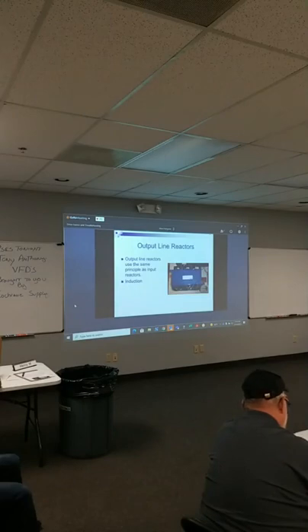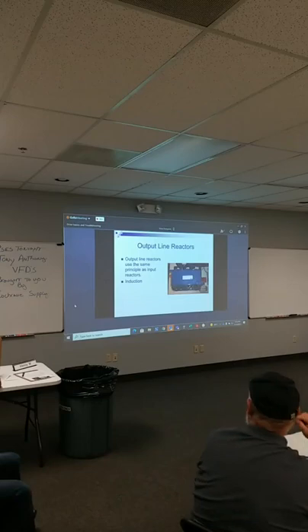Output line reactors, once again, MTE is a very famous, common line reactor. It is the exact same components, basically a fancy coil of wire, and it uses the same principle because they are the same. So what we're doing with the output line reactors, instead of getting rid of the harmonic distortion, is protecting that motor from those high voltage peaks I mentioned, because the way we're pulsing that DC, the peaks are always the same height, and then they get some overshoot. This will actually help squelch that down a little bit and protect that motor from some of the heat.